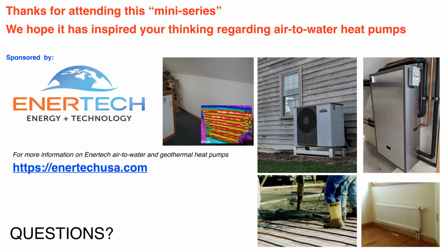So the answer is yes, you could wire the pump so that if you have electric zone valves and everything is off, you could shut the pump off. But in a system where you're using non-electric valve-based zoning, there's no problem in letting that pump just go down into that sleep mode. It uses pennies a day of electricity, and it's, as I say, a very common application in the European market. Not as well known yet in the North American market, but I suspect that it will be.